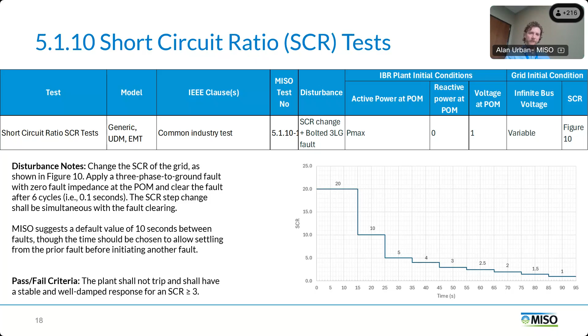So basically, we step through a number of SCRs to determine if the plant will trip or not. We don't expect the plant to trip for any SCR greater than or equal to 3. Although we do specify tests below 3. This is more just to observe the response of the unit, but you would be considered passing otherwise if you were able to maintain stability if the SCR is greater than or equal to 3.